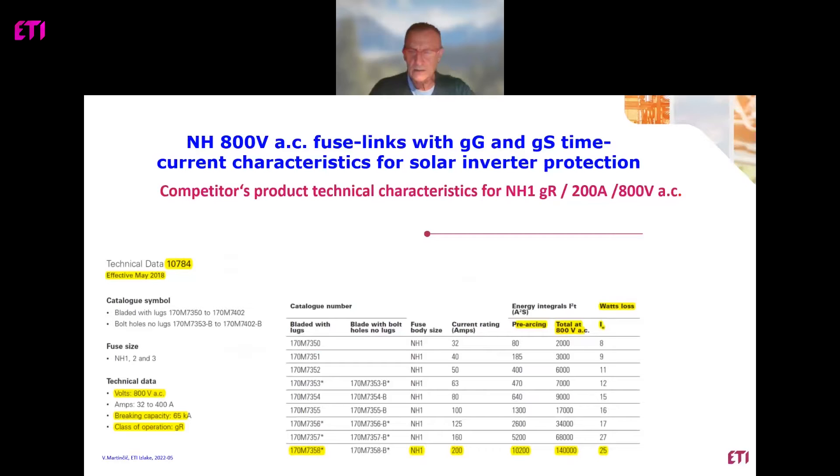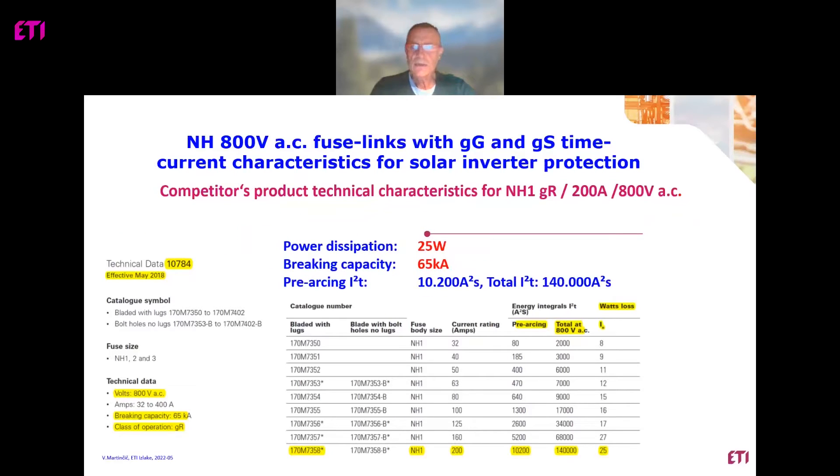From customers we are receiving a lot of information about the use of so-called semiconductor fuses for the protection of outputs of inverters. There is a competitor's product with technical characteristics designed for 800V AC, breaking capacity 65 kilo-amps, and characteristic gR. This fuse is very good, but we need to know that the application where such a fuse is installed should be very carefully calculated. Power dissipation is 25 watts and breaking capacity is 65 kilo-amps. There is also information about pre-arcing integral and total integral of the fuse.